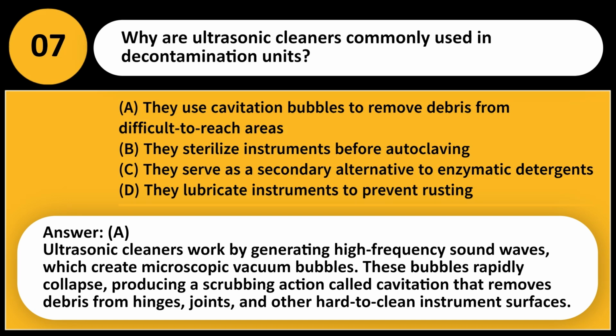Ultrasonic cleaners work by generating high-frequency sound waves, which create microscopic vacuum bubbles. These bubbles rapidly collapse, producing a scrubbing action called cavitation that removes debris from hinges, joints, and other hard-to-clean instrument surfaces.